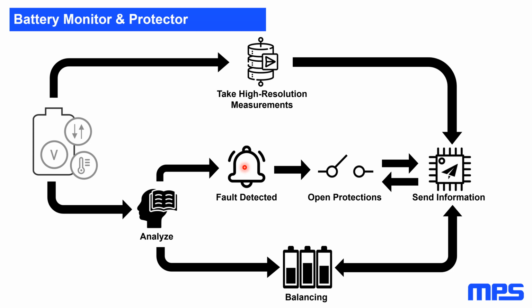Finally, we find the over and under temperature fault, which is also important. After detecting any of these faults, it's a huge advantage if the battery monitor and protector can directly control the protection FETs. Having this direct control using an integrated high-side FET driver ensures better protection of the battery.